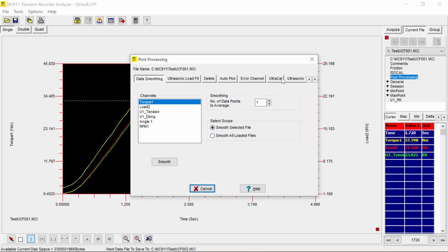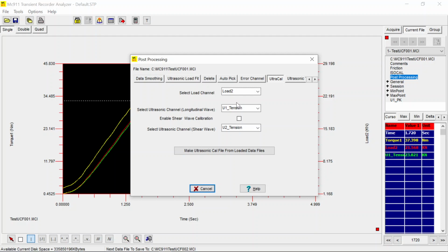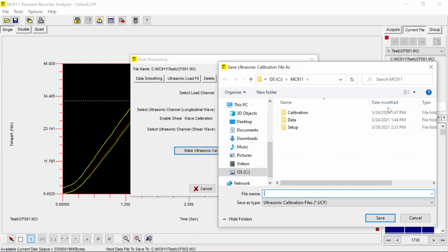There's a tab here called UltraCal. UltraCal means it takes two channels, then it creates an average, a UCF file, an ultrasonic calibration file. First, you have to select your load channel, which is what we had, load 2. Then select your ultrasonic channel, which is U1 tension. Don't mind this one; it's for dual sensor type calibration, which involves another sensor. We don't have that in this particular data collection. So click on make ultrasonic cal.